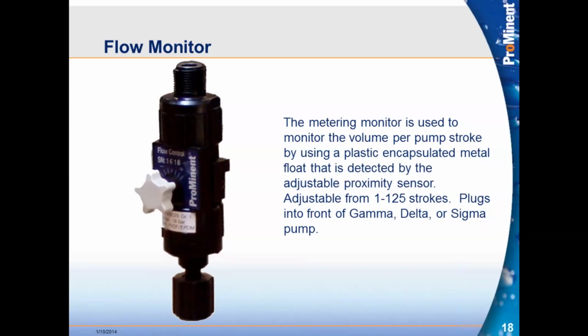What this device does is it verifies that after the pump stroked, it delivered a volume out of the discharge. We don't necessarily know what that volume is, but we deliver enough volume that we can actuate this device if we've set it properly. And every time we change the volume per stroke, the stroke length is what controls that, we have to change that adjustment on the front of this metering monitor. So now that feedback goes back into the pump, and the pump knows when it discharged. It expects that signal back from this device in a timely manner.